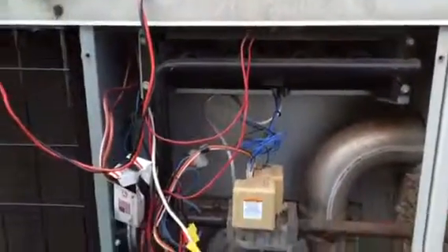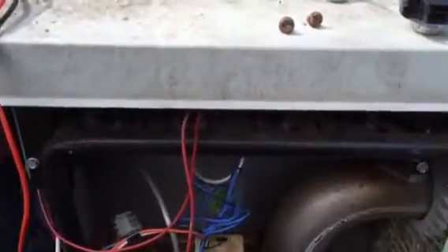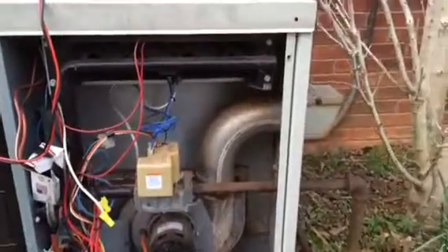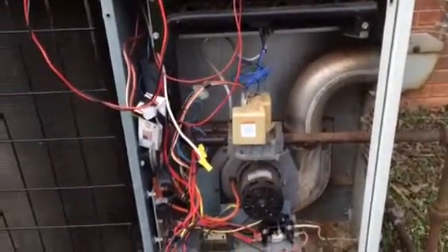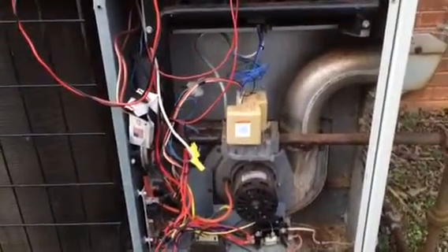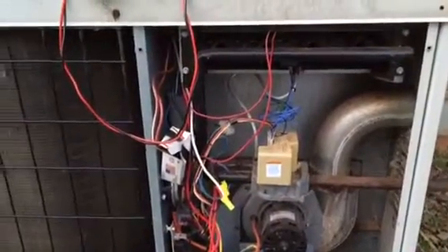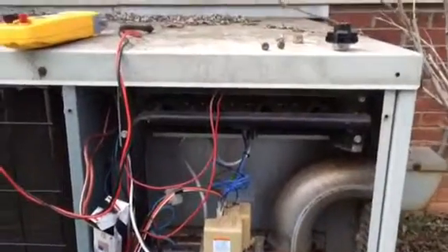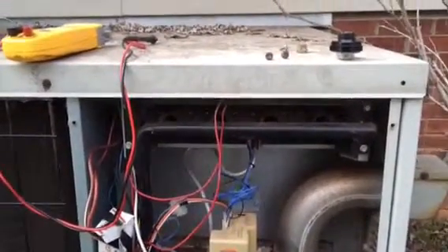The other reasons, and sorry to mention them out of order: clogged orifices, not getting enough gas flow, a cracked heat exchanger with oxygen coming in contact with the natural gas and pushing the heat back towards the rollout switch, dirty orifices, a dirty filter, not enough airflow, and a bad switch. So we're going to go with bad switch today, and hopefully that'll take care of it and we won't have to come back out.